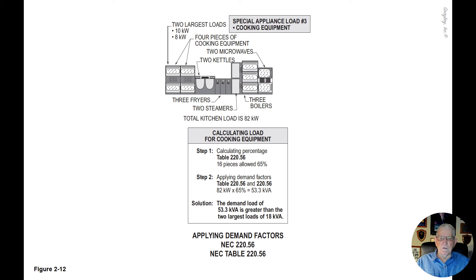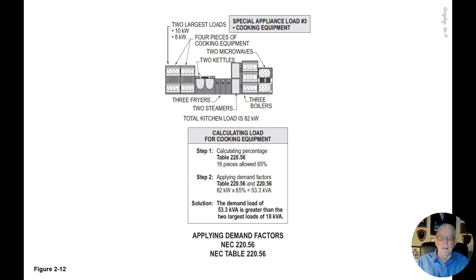This illustration deals with applying demand factors for cooking equipment in commercial or industrial locations in accordance with NEC 220.56 and Table 220.56. Notice that we used Section 220.55 and Table 220.55 along with its notes for residential. But since these types of cooking equipment may be in a restaurant, we would use Table 220.56 to determine the VA for these loads after a demand factor has been applied.